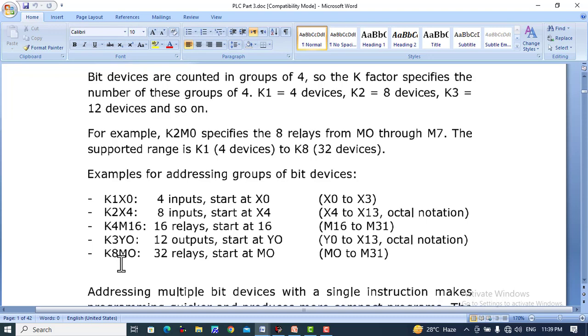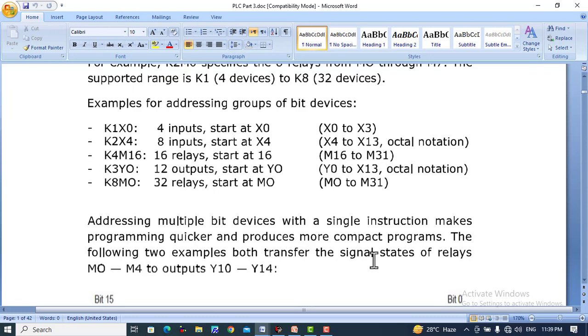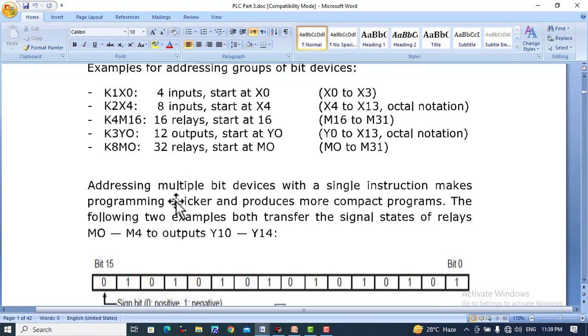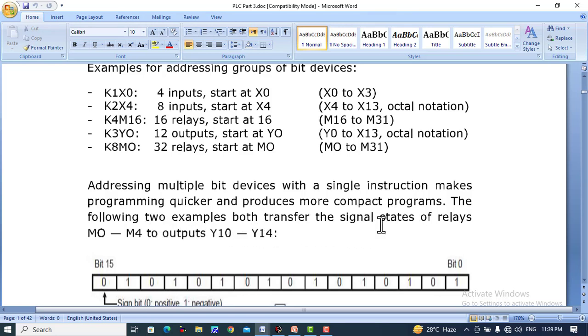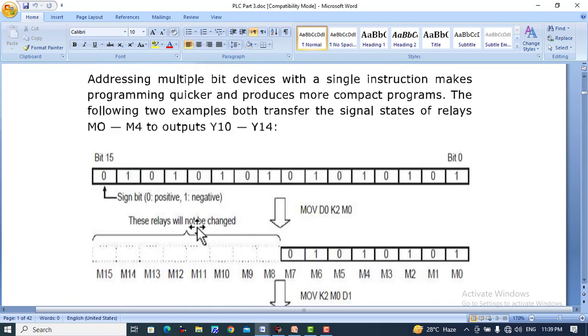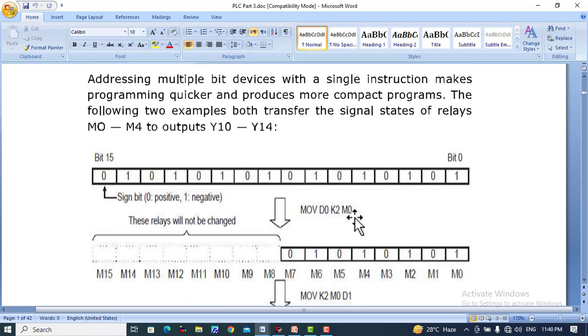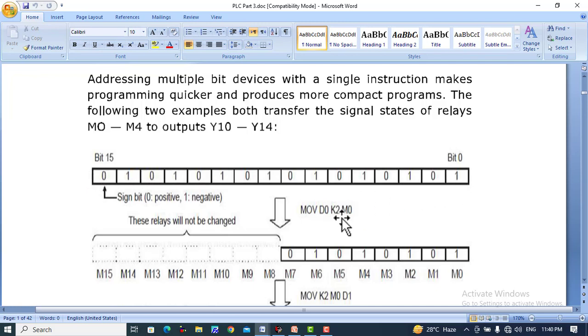Addressing multiple bit devices with a single instruction makes programming quicker and produces more compact programs. The following examples both transfer the signal states of relays. Here's an instruction: MOVE D0 K2 M0. D0 is a 16-bit register. It will move K2, meaning eight values, starting from M0 to M7.